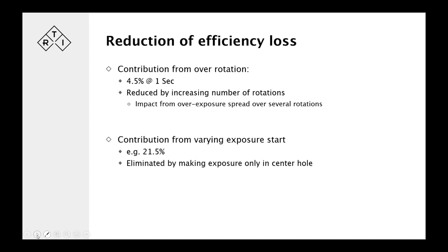And the contribution from varying exposure start, well, that's eliminated because we're exposing only in the center hole where we have symmetry and there's no influence. It doesn't matter where, on the rotation, the tube starts firing. So we can get rid of that.